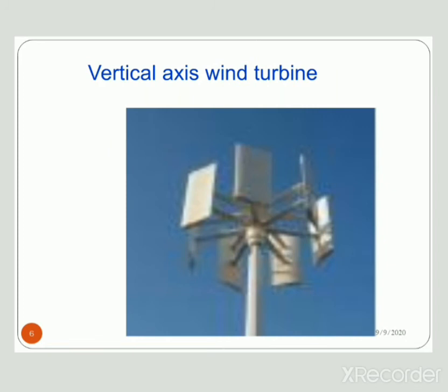The vertical axis wind turbine has advantages. These turbines have fewer parts than those that orient the rotary mechanism and blades horizontally. That means fewer components to wear out and break down. Also, the supporting strength of the tower doesn't need to be so much because the gearbox and generator are near the ground. So parts for controlling pitch and yaw aren't needed either.